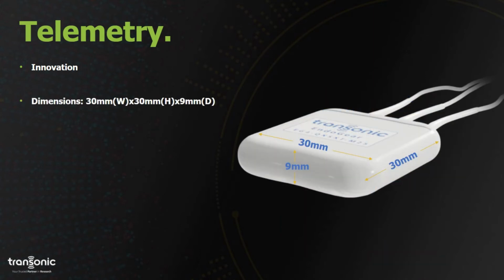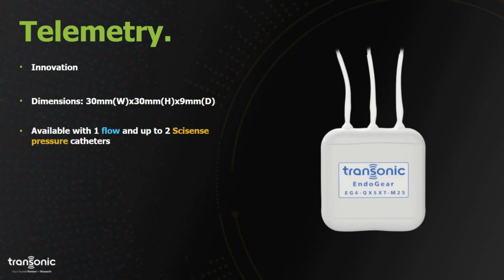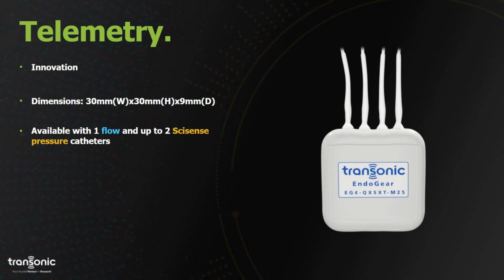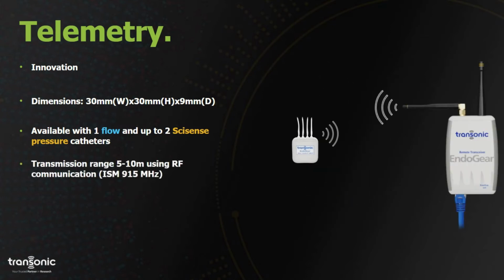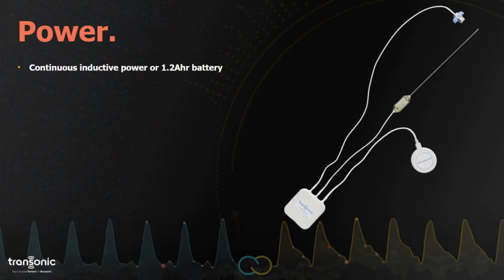Ultimately, the dimensions now are 30 millimeters by 30 millimeters by 9 millimeters, as you can see in the measurements there. These implants are available with 1 flow and up to 2 Scisense pressure catheters. So in this orientation that has 4 outputs, we'll talk about power shortly, but 3 of those would be taken up, 1 for flow, 2 for pressure, and then 1 for power, which we will get to shortly. The transmission range of the implant is roughly in the neighborhood of about 5 to 10 meters using RF communication. I use the term roughly, and again, we'll talk very briefly about what that transceiver is and how it works and some of the things that go into differentiating how far something can actually transmit. So we'll get to that very shortly. And then, of course, included with all of the implant variants is internal temperature to measure the temperature of the animal, and also activity data via an accelerometer.